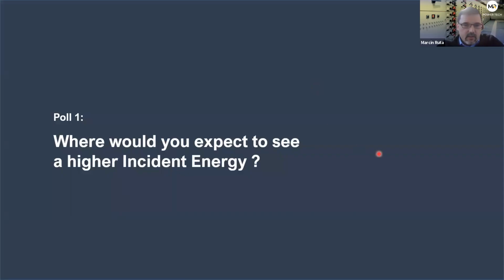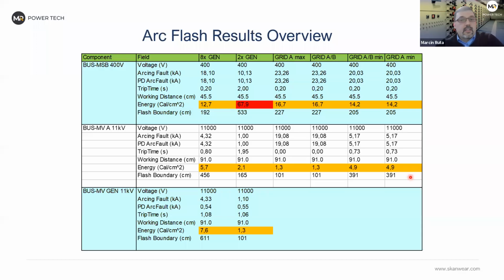So before we jump further, I just want to give you a question. Where would you expect to see a higher incident energy? Will it be at the low voltage part of the installation or at the medium voltage part of the installation, 11 kV? To keep it short, take your time to vote. And we'll keep it open for a few seconds more, and then we go for the answers. Yeah, so it's quite good actually. We will see it at the low voltage part.